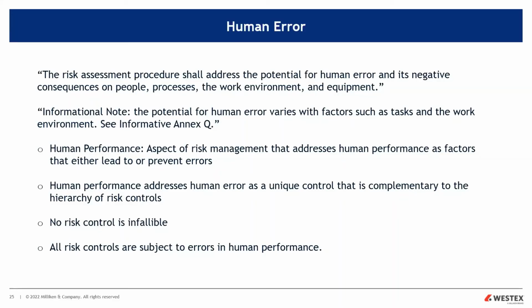So when we look at NFPA 70E in the latest version, the risk assessment procedure shall address the potential for human error and its negative consequences on people, processes, the work environment, and equipment. And it has an informational note. The potential for human error varies with factors such as tasks and the work environment. See informative Annex Q. Now, of course, informative Annex Q and the informational notes are not required to comply with 70E, but some really, really good information I suggest you look at.